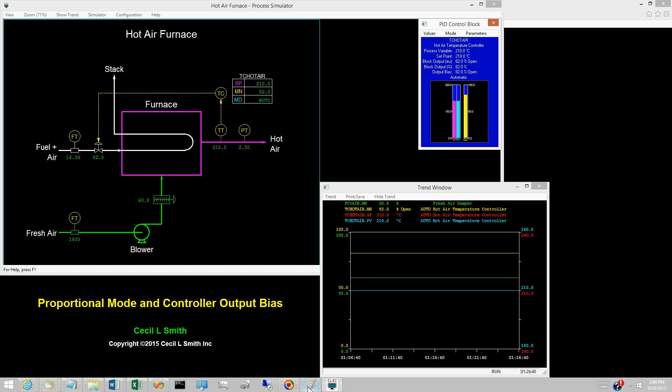Proportional only controllers have one major defect. When a loop lines out, the usual expectation is that the PV will equal the set point. But for proportional only controllers, this is not assured. At line out, the control error must be constant, but not necessarily zero.